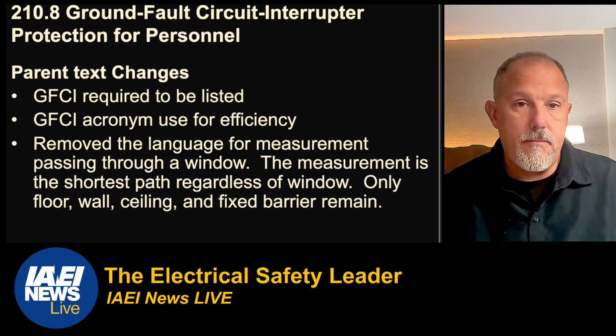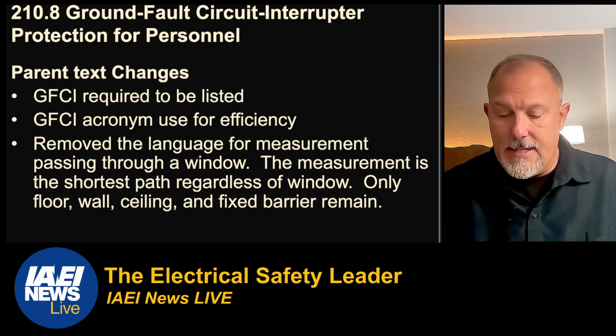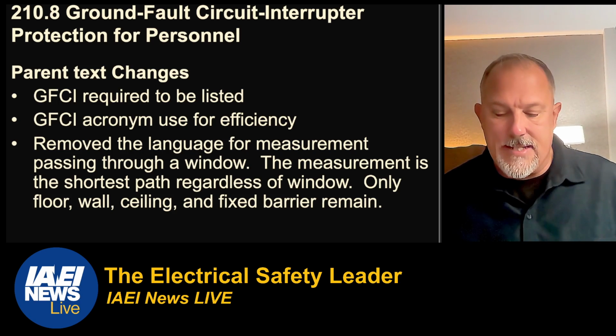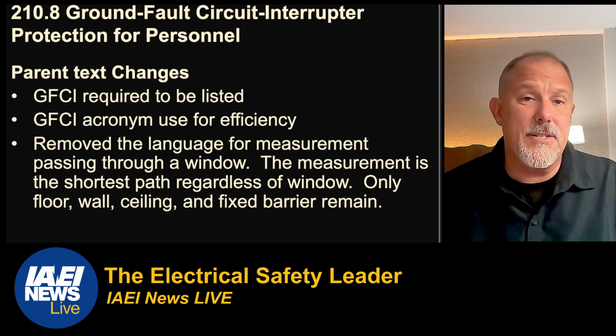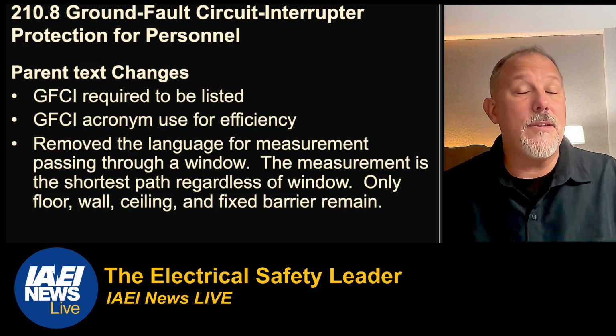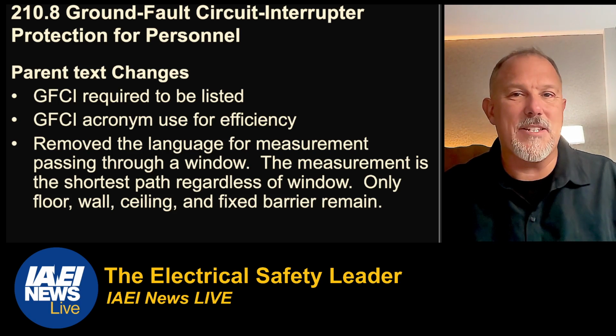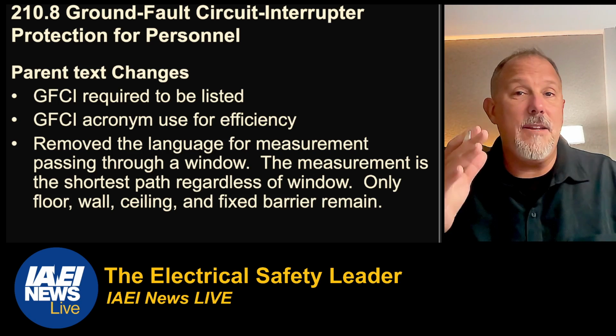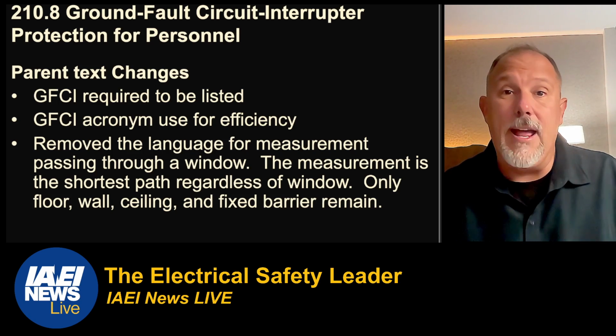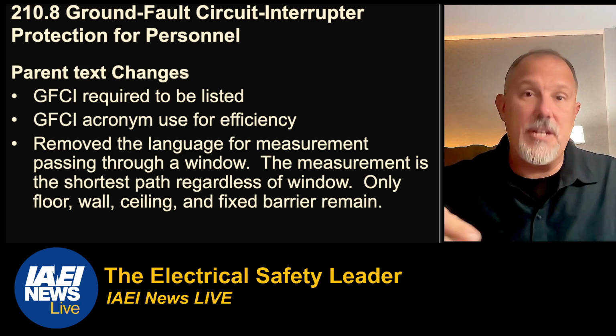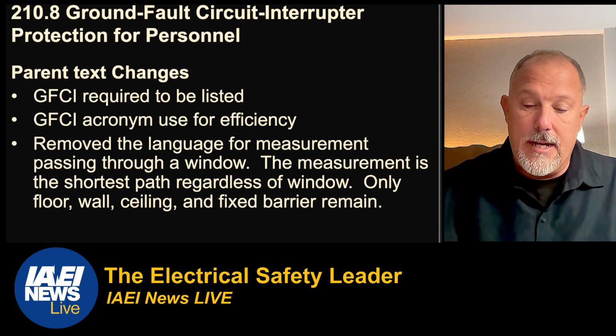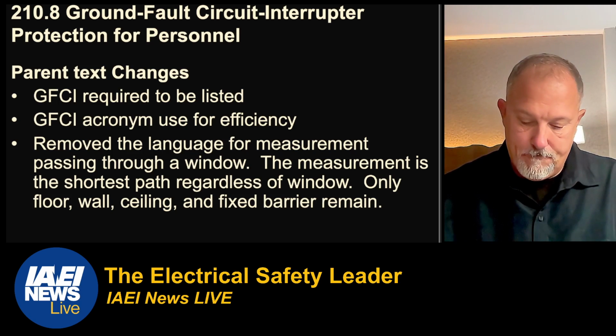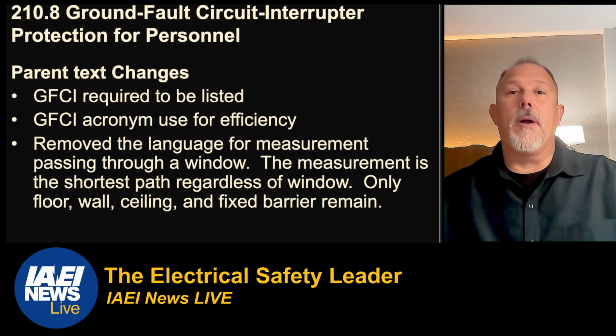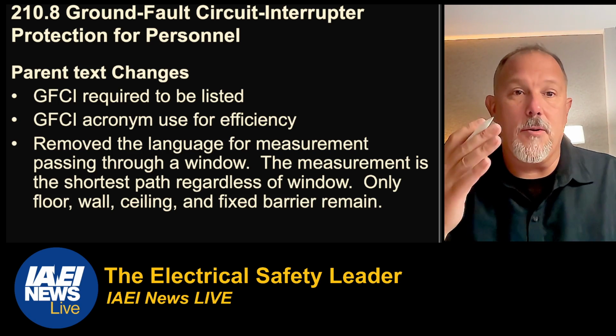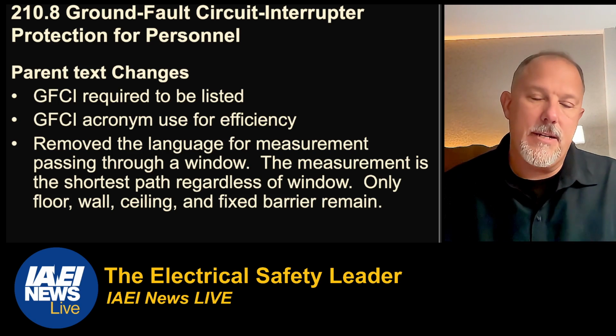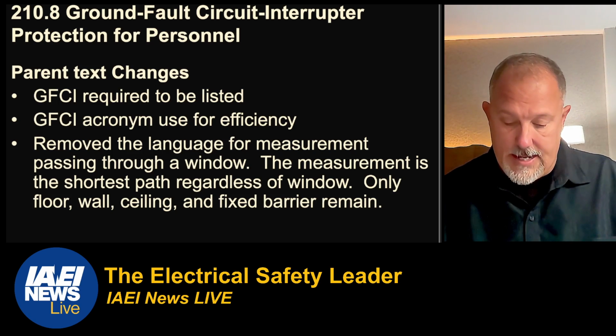All right, so in the parent text of 210.8, now you might say, look, Tom, we're going to buy listed GFCIs anyway. But in the code, we didn't really point out that the ground fault circuit interrupter has to be listed. In fact, we didn't point out in any previous editions that a molded case circuit breaker had to be listed. So those changes are a part of the 2023 code cycle. You probably already bought listed circuit breakers. You probably already purchased listed ground fault circuit interrupters. So not necessarily a big change, but it is a level of awareness that they have to be listed.